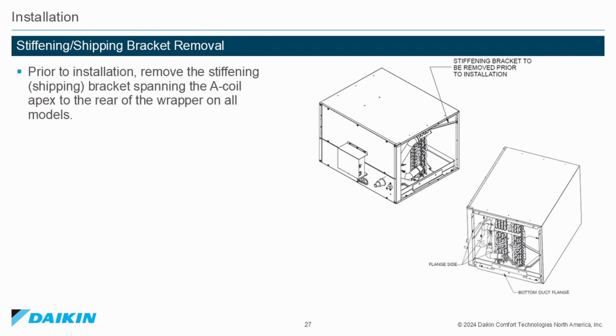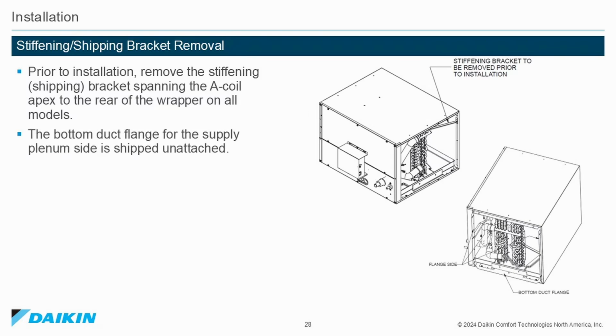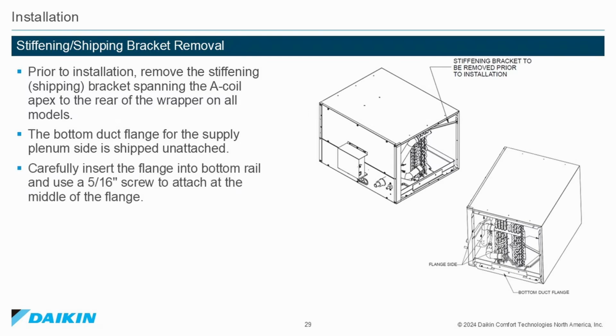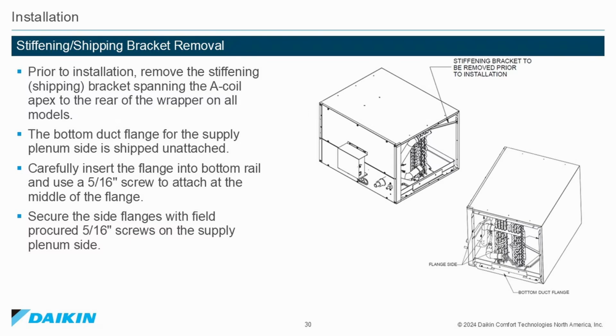Stiffening or shipping bracket removal. Prior to installation, remove the stiffening or shipping bracket spanning the A-coil apex to the rear of the wrapper on all models. The bottom duct flange for the supply plenum side is shipped unattached. Carefully insert the flange into the bottom rail and use a 5/16" screw to attach at the middle of the flange. Secure the side flanges with field-supplied 5/16" screws on the supply plenum side.